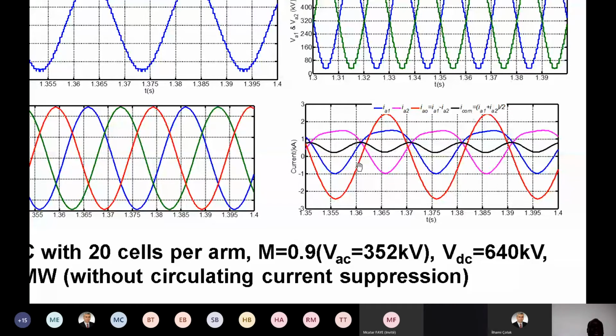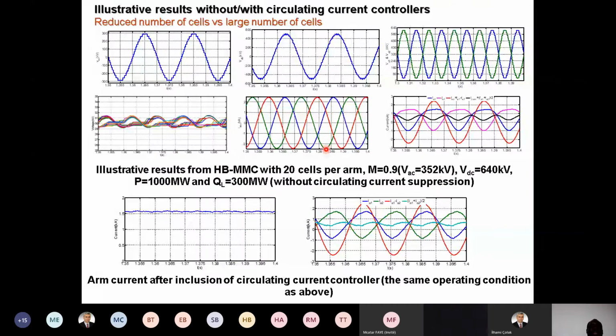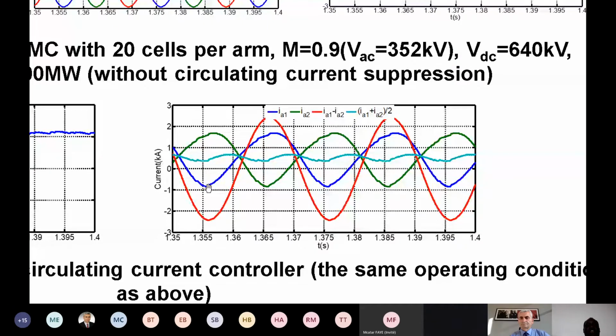And this one here is the same case, where we just include the circulating current controller. You can see now it's not perfectly eliminated, but if I zoom here, you can see the upper and lower arm currents are slightly much better, and the common mode becomes almost DC. But there is still some remnant second harmonic on them, while the differential mode remains unaffected.